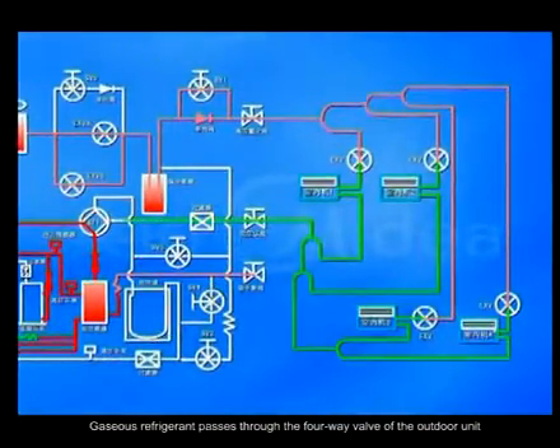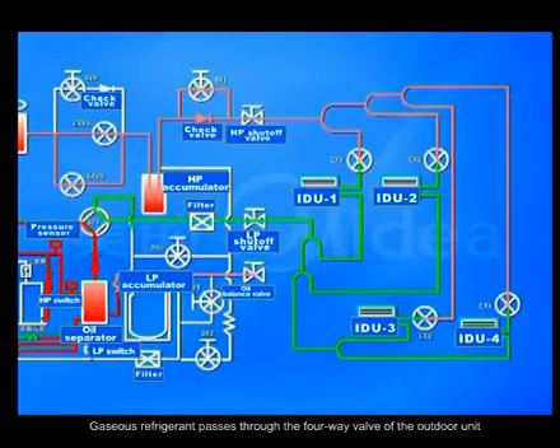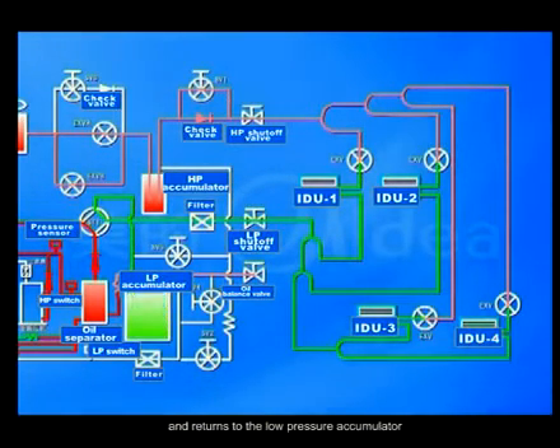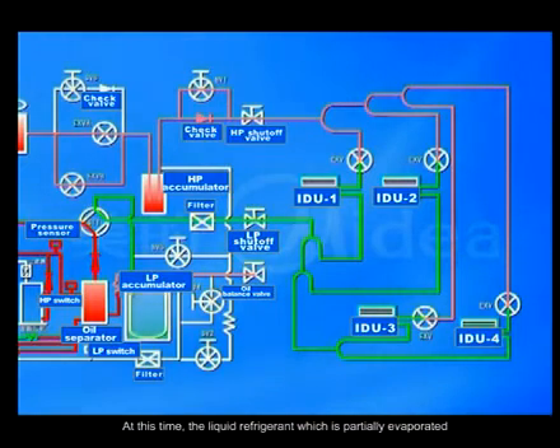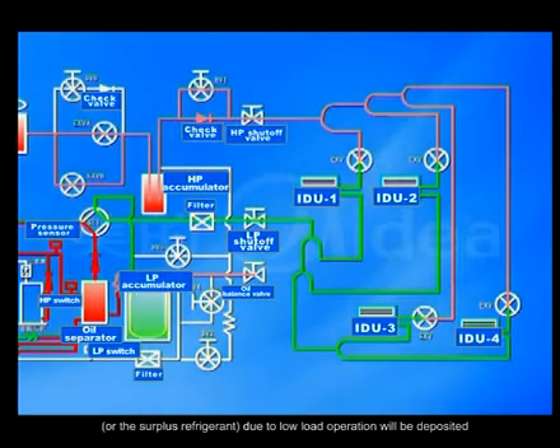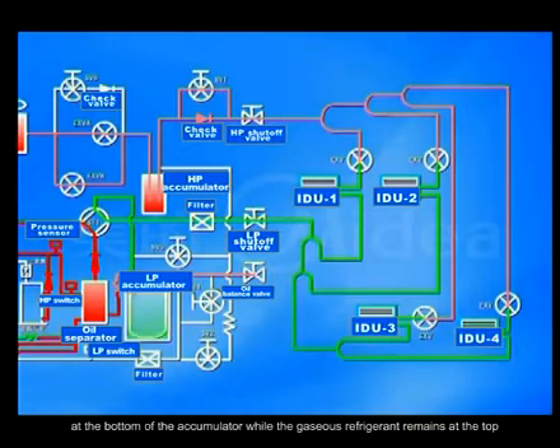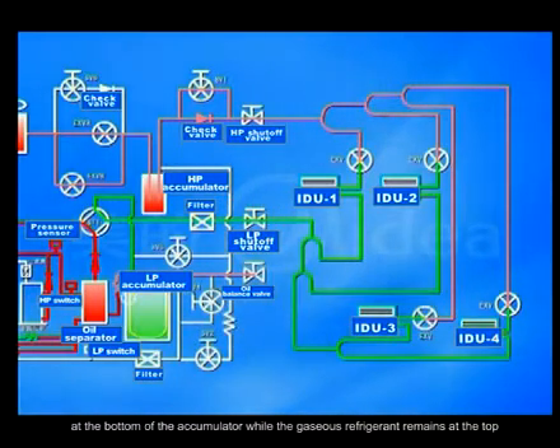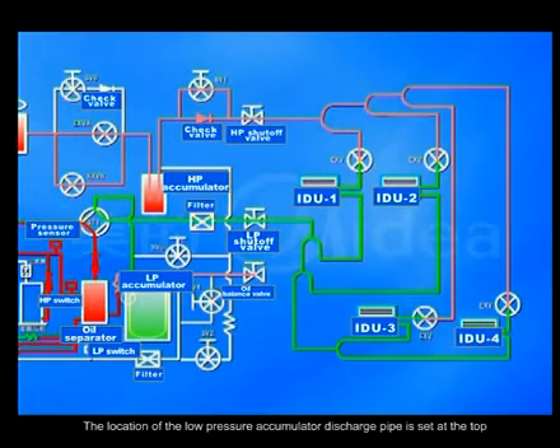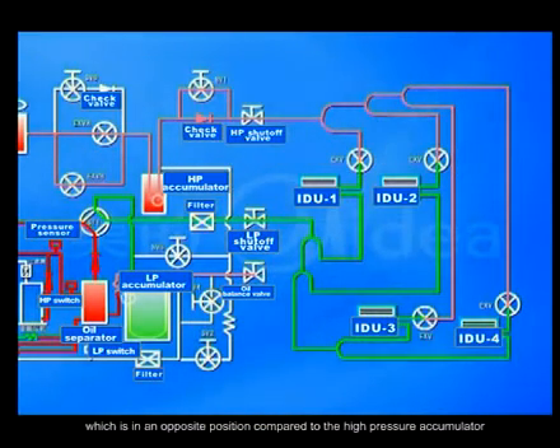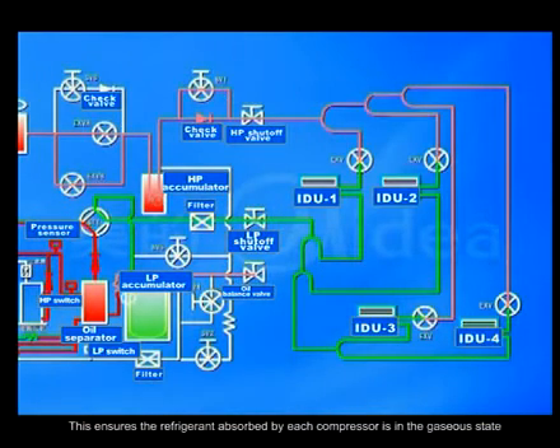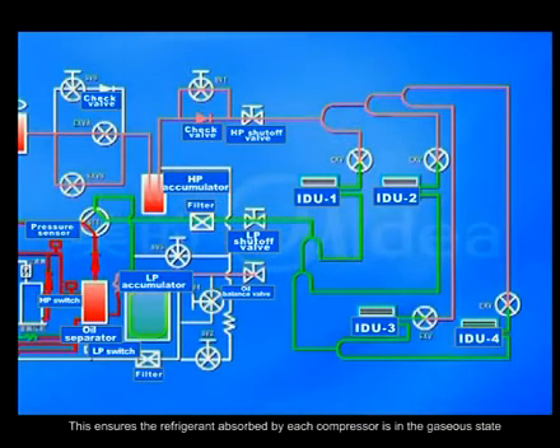Gaseous refrigerant passes through the 4-way valve of the outdoor unit and returns to the low-pressure accumulator. At this time, the liquid refrigerant, which is partially evaporated, or the surplus refrigerant, due to low-load operation, will be deposited at the bottom of the accumulator, while the gaseous refrigerant remains at the top. The location of the low-pressure accumulator discharge pipe is set at the top, which is in an opposite position compared to the high-pressure accumulator. This ensures the refrigerant absorbed by each compressor is in its gaseous state.